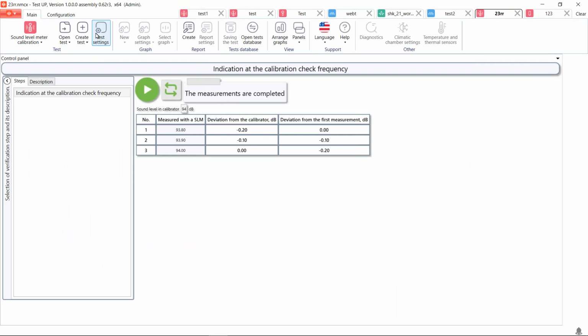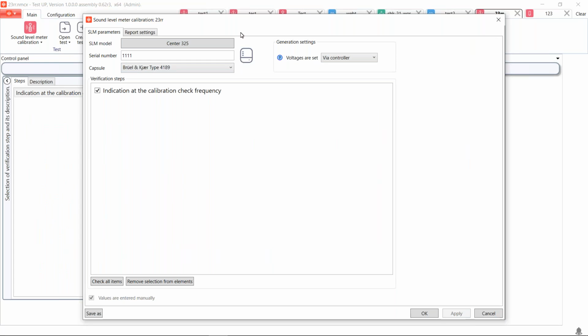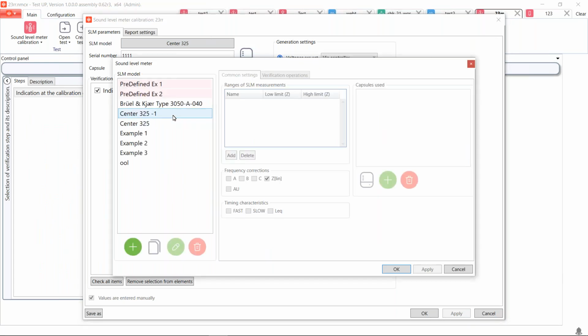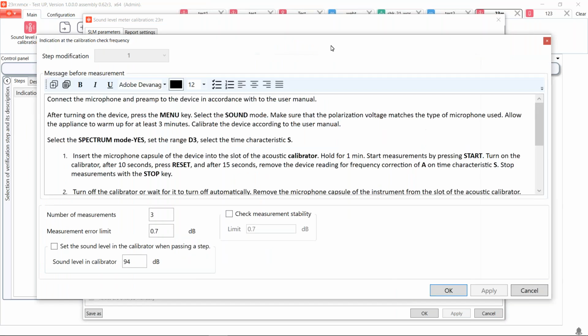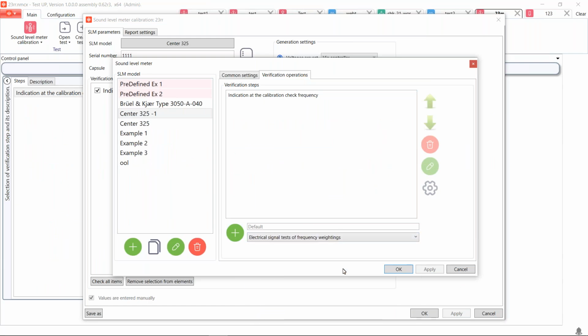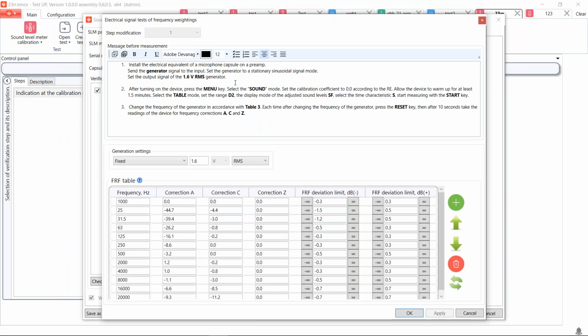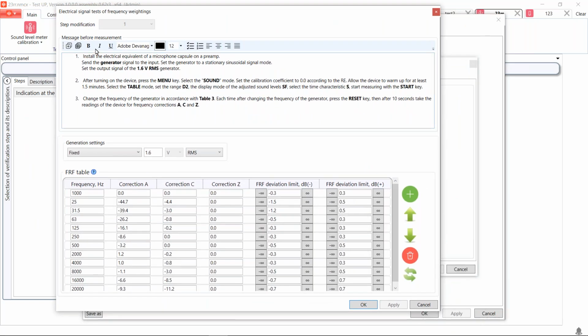microphone. So let's open test settings and continue to work in the sound level meter we created. So we add another step. As it was in the previous step, there is also the description of the step you need to perform in accordance with the standard of this procedure. The test procedure in this case consists in applying an electrical signal from the output of the control system to the input of the sound level meter, bypassing its microphone. Measurements are made by scanning over the entire frequency range.